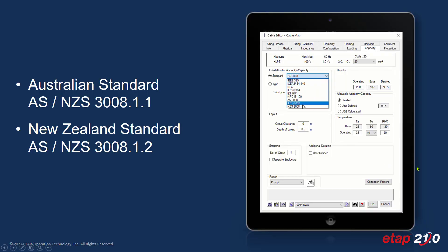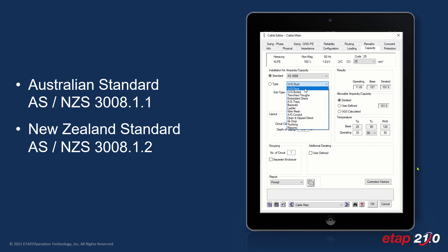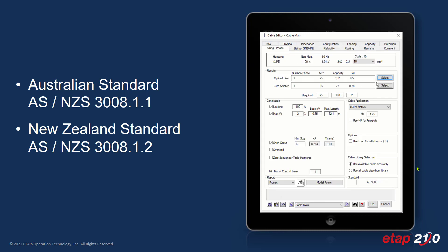For those familiar with the cable editor and cable sizing within ETAP, we can go right into the capacity page, select the applicable standard — whether that's Australia or New Zealand — select your installation type, and ETAP automatically calculates the derated values. You can change the size directly from the editor and view your new results, or from the sizing tab, select the optimal size provided or one size smaller.